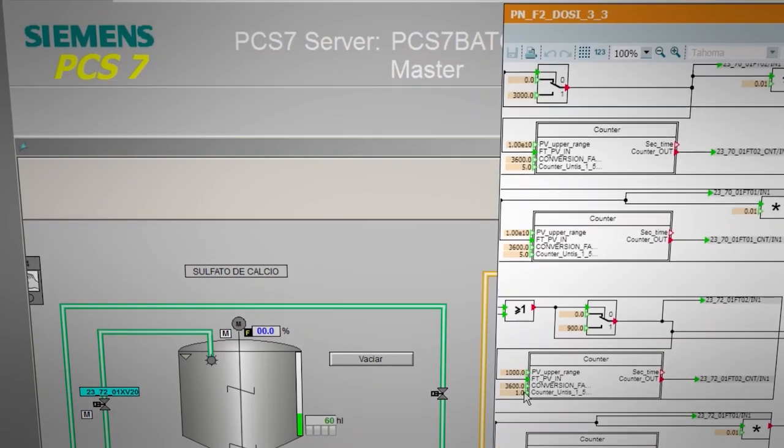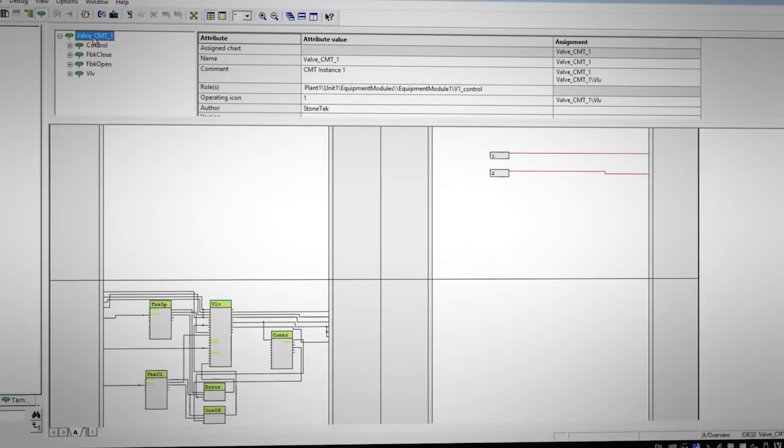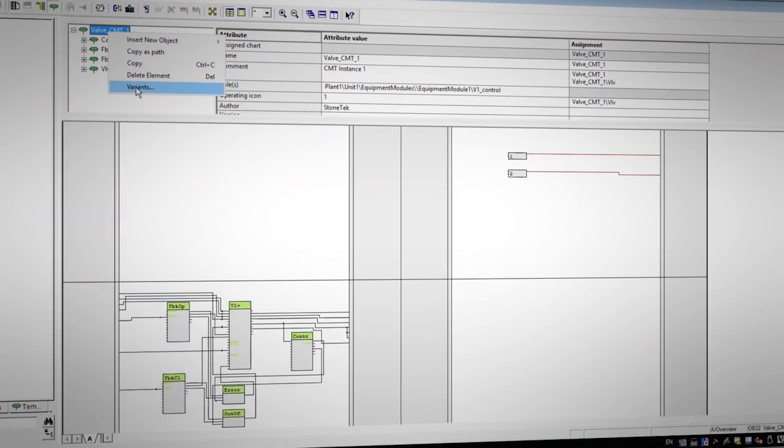on the market. The Siemens Advanced Process Library, or APL, is nice because it is a standardized library with common functions that the majority of customers have all the functions they need, and then it has feature bits that allow you to turn off and on very detailed pieces of logic for a specific customer or a specific function.